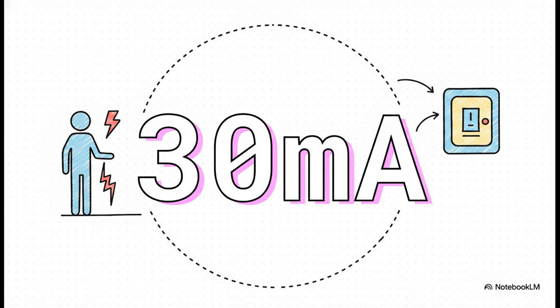If you were to accidentally touch a live wire, the electricity would bypass the neutral return and travel right through you. The RCD instantly detects that missing 30 milliamps and trips, quite literally saving your life on the spot.